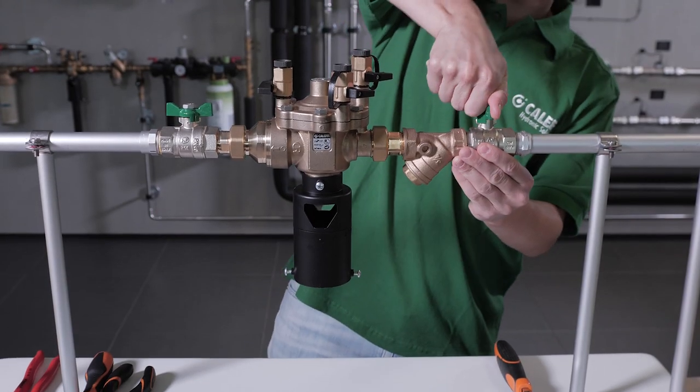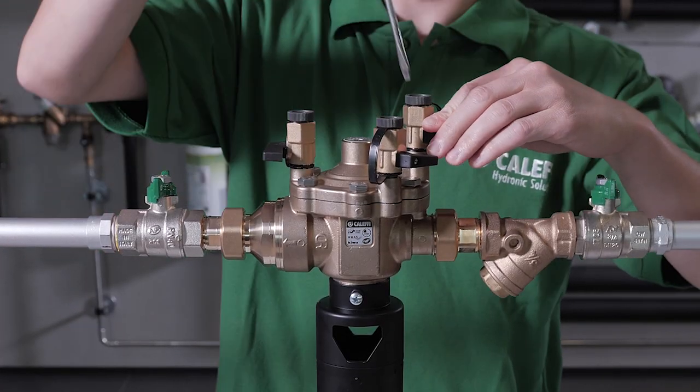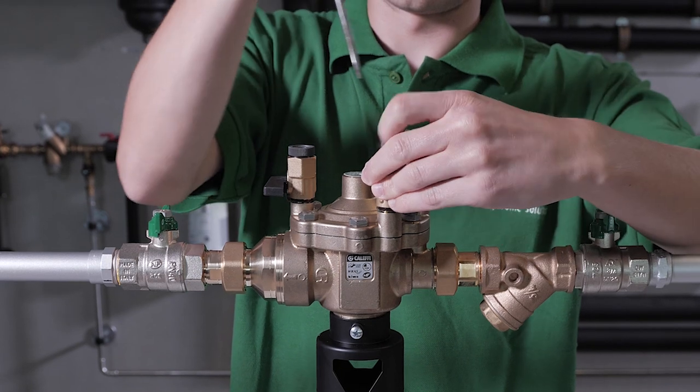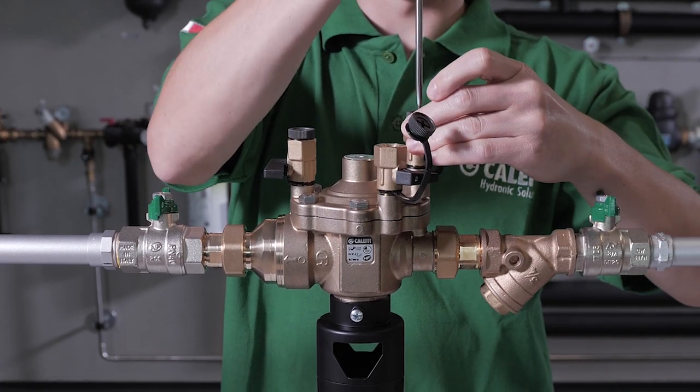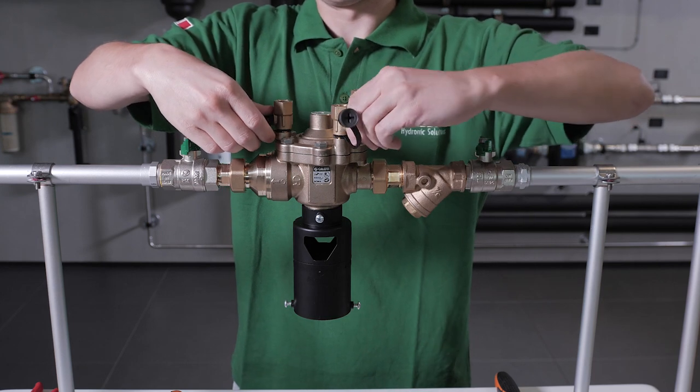Close both the shutoff valves and then vent the air out of the unit with the aid of the pressure ports on the top part of the backflow preventer. This way, the water content in the unit will be discharged.